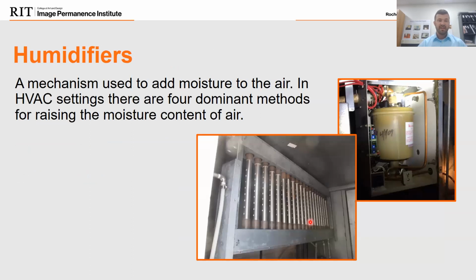It is a mechanism used to add moisture to the air. In HVAC settings, there's really 4 dominant methods. The 2 that we see the most often are these canisters and these tubes that appear to have little holes down them. Basically, this will create steam as the air passes over it. The air will pick it up and it'll blend, if you will, and move downstream with the air, changing the moisture content. And this is the little boiler. It'll boil the water in this canister, send it through a tube into the unit, and again, reject that steam in a similar fashion to this, which will help move it downstream as well.